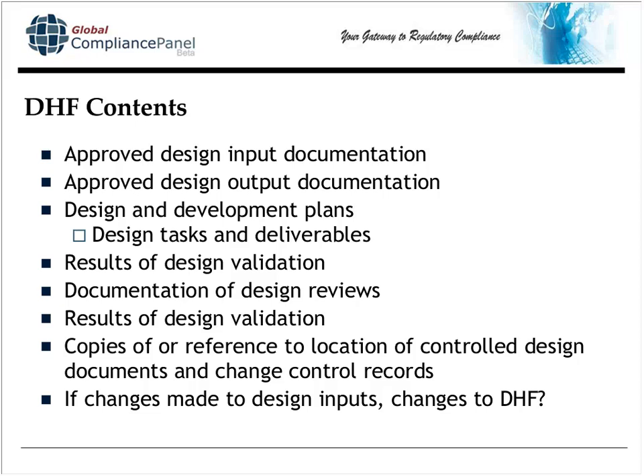Also in the DHF are the design and development plans — what you plan to do in each phase and throughout the entire process — including deliverables usually shown as Gantt charts or Microsoft Project plans. When it comes to what the FDA expects to see, your first plan is barely a plan, but as you move forward the plan becomes more concrete. The FDA inspector will expect to see more than one of these Gantt charts, because part of showing your design and development plan is showing that plan as it iterates and changes. Showing only the last plan — the one you met — is not really showing your planning process.